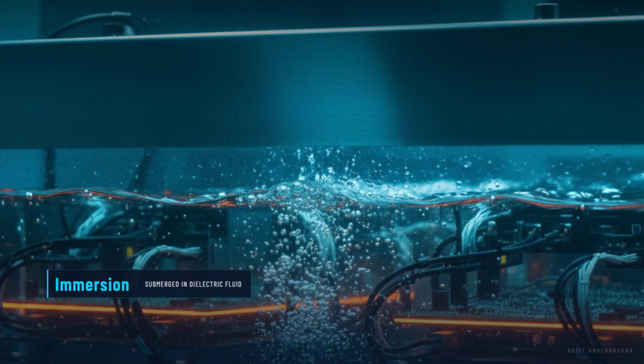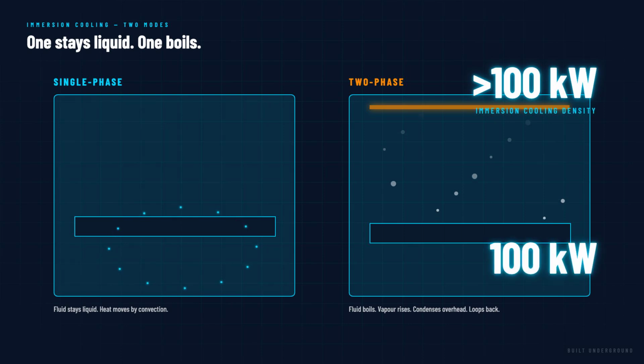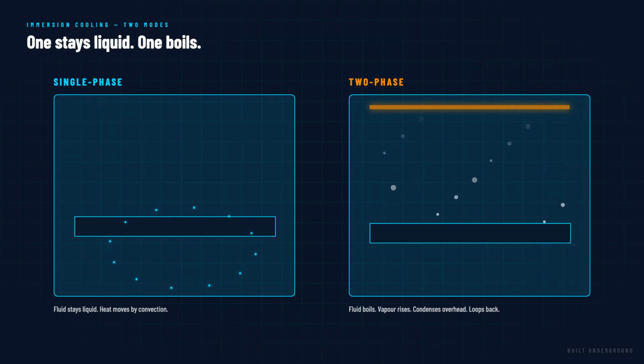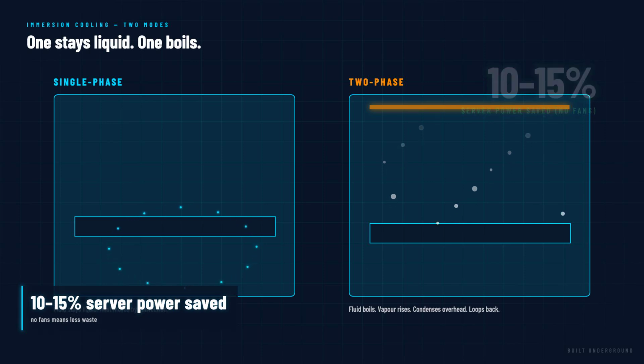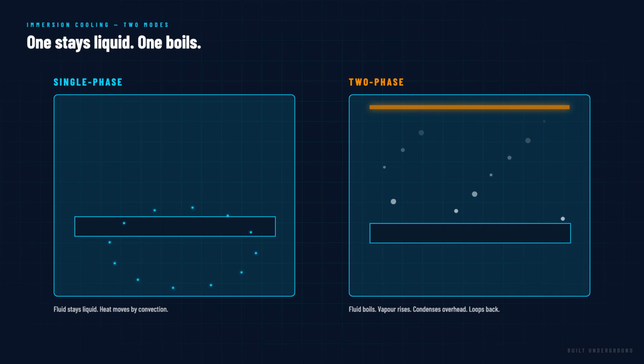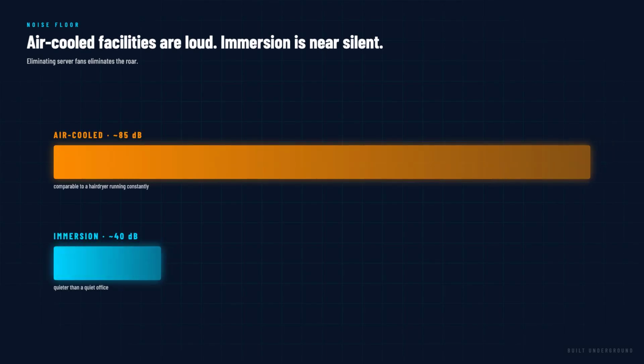Immersion cooling can handle rack densities above 100 kilowatts. It eliminates fans entirely, which reduces server power consumption by 10 to 15%. It cools every component evenly, eliminating hot spots, and it operates nearly silently. The trade-off is operational complexity. Servicing hardware means draining or extracting boards from fluid. The dielectric fluids themselves are expensive and some have environmental concerns, and the mechanical infrastructure, tanks, fluid management, leak detection and containment adds design and construction cost.